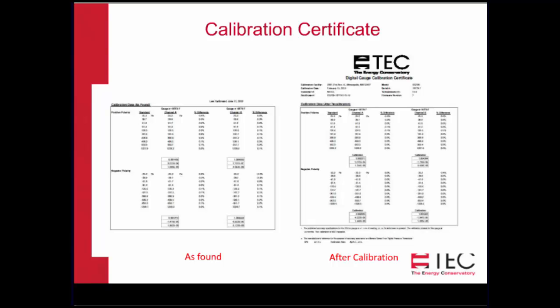We've also been asked occasionally, what is the accuracy of the DG700? At the bottom of the digital gauge calibration certificate, there is a statement which says that the instrument has been tested to an accuracy of plus or minus 1%, plus or minus 0.15 pascals. So you can always go to your calibration certificate to find out that information.